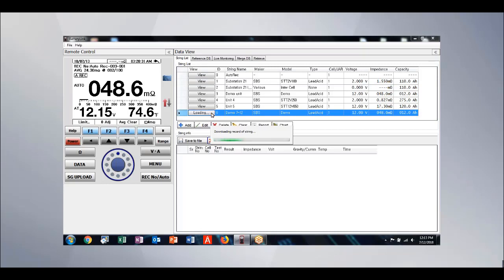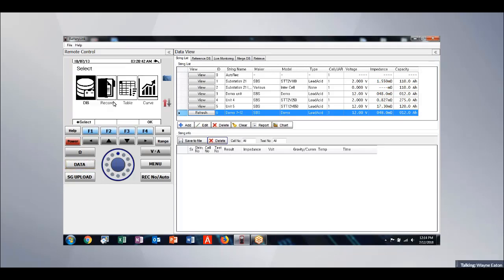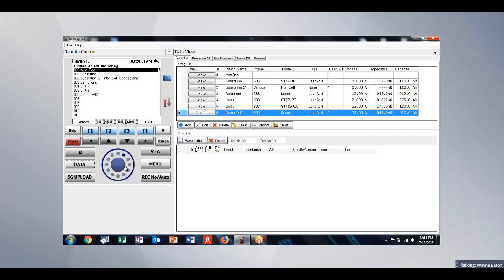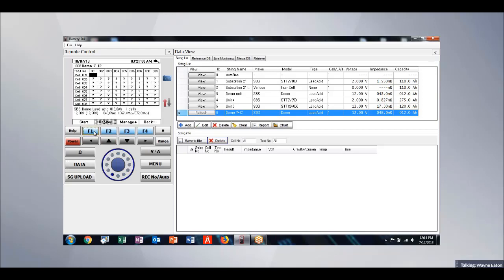So if I hit view right now, I have no readings. I have never taken a reading for that location. But if I look at the data by pressing the data button on the unit, and then I scroll over to record, and I press down on the rotary key, and then I scroll down to that demo 7-12. And I go in and look, I'm set up for test number 1, cell number 1 in the string, demo 7-12, and it's going to allow me to measure up to 250 cells in that first test.